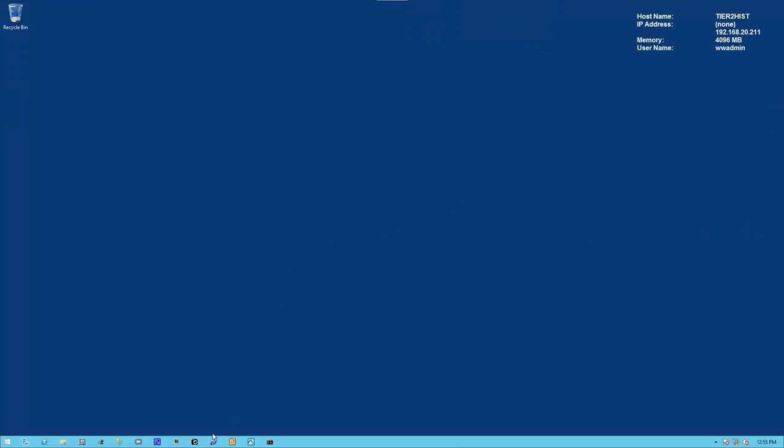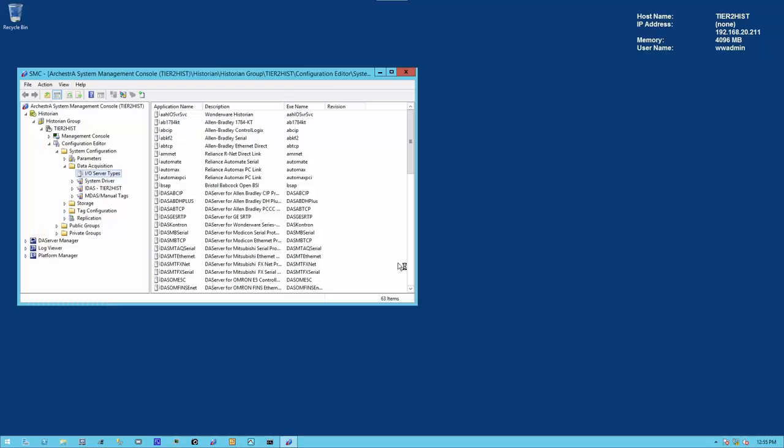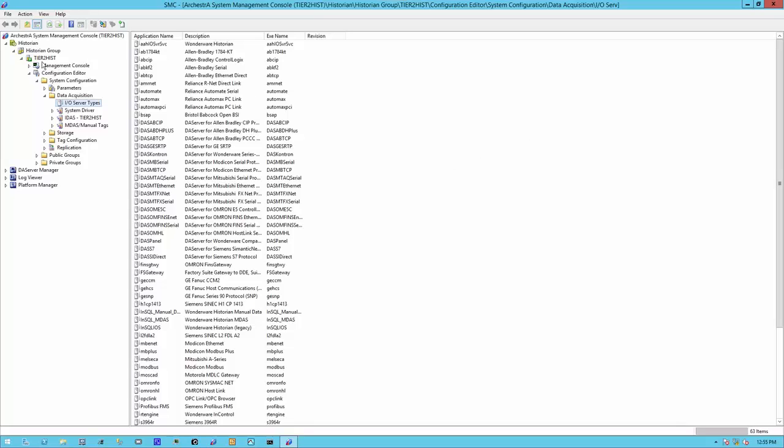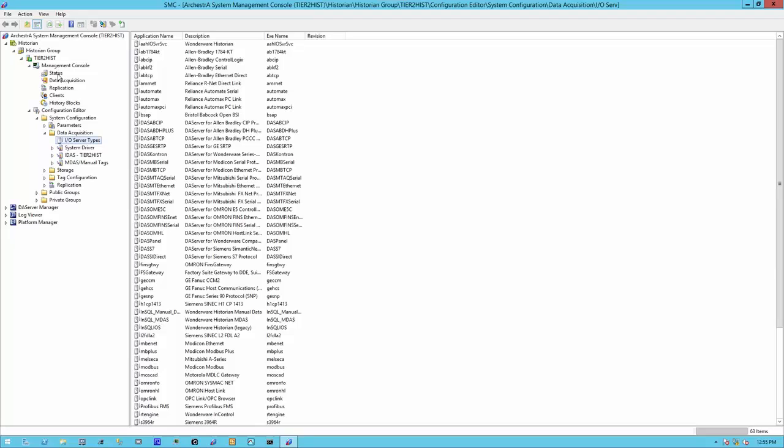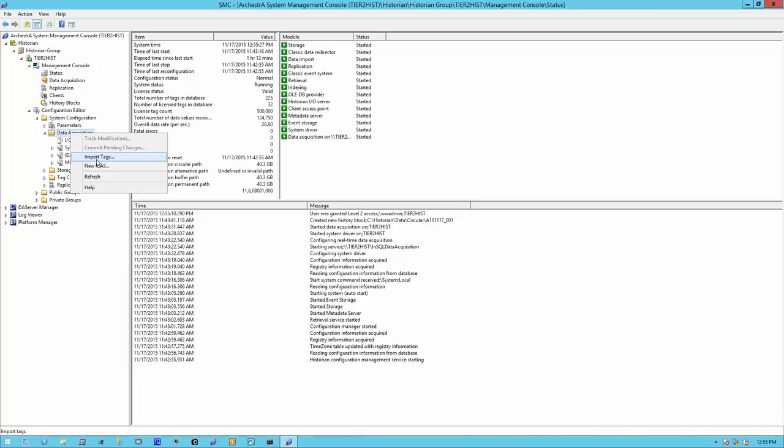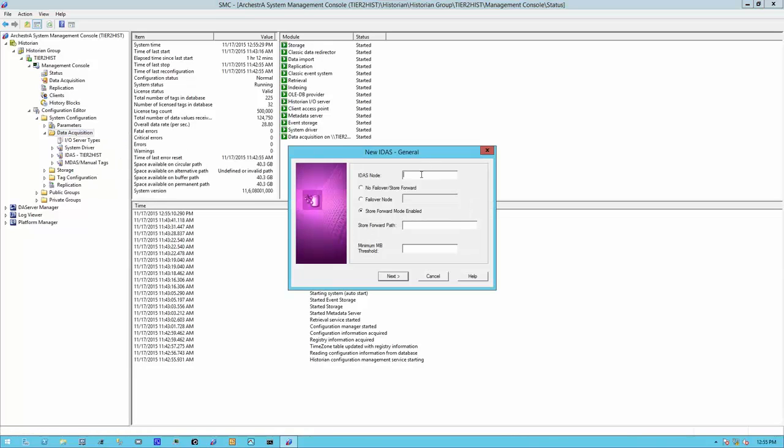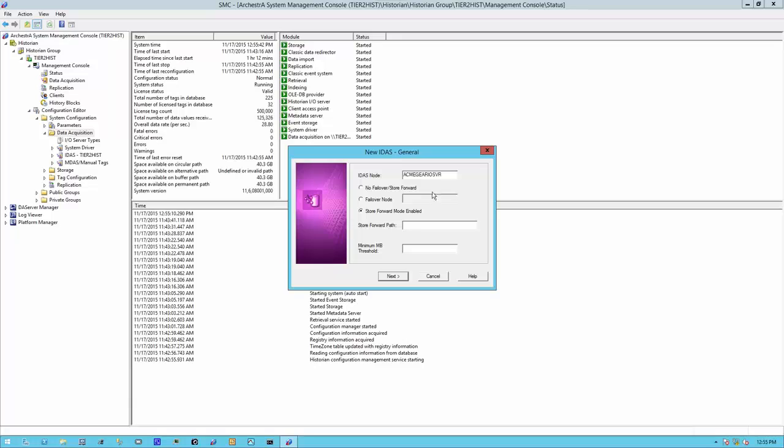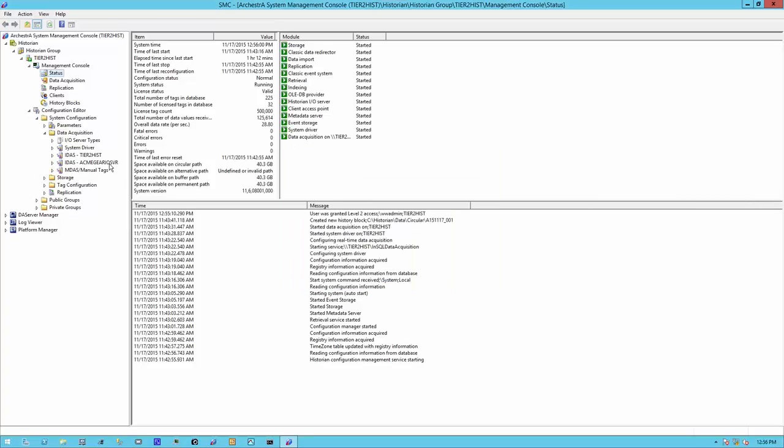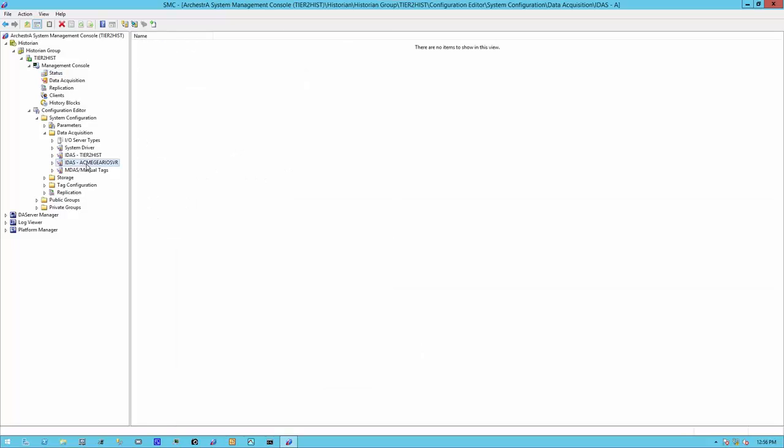On the historian, let's open up the system management console. Here you see my historian and the configuration editor and the management console. We verify that the historian is functioning as we expect. Now let's create a new IDAS. For the IDAS node, let's give it the name of our IO server, or where the remote IDAS is installed. Let's create a store forward directory and set a minimum megabyte threshold. We can go with the defaults. We've created our new IDAS. Let's commit pending changes.